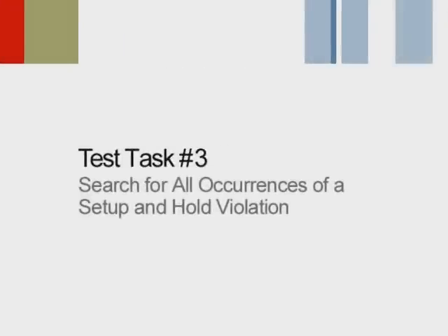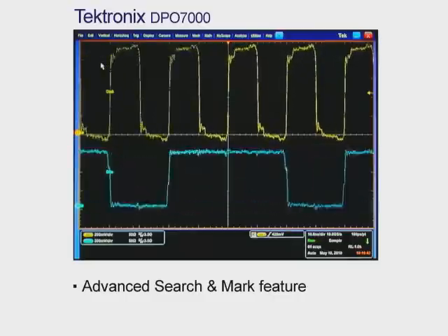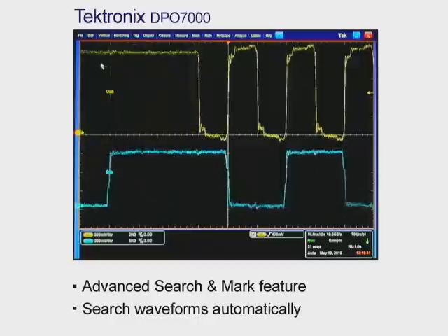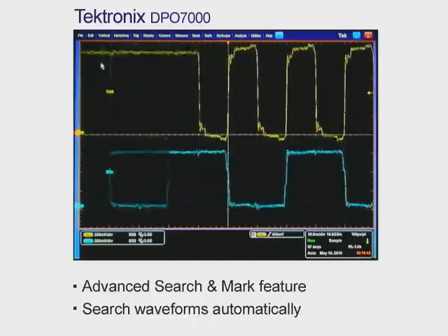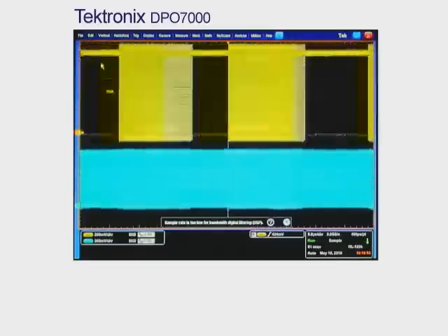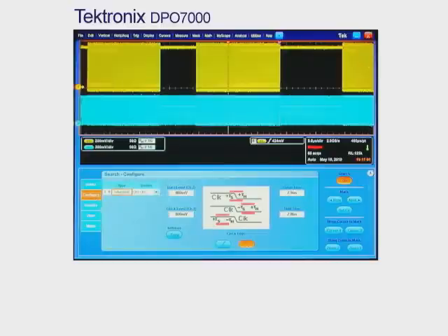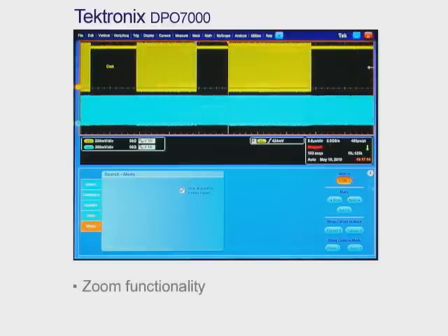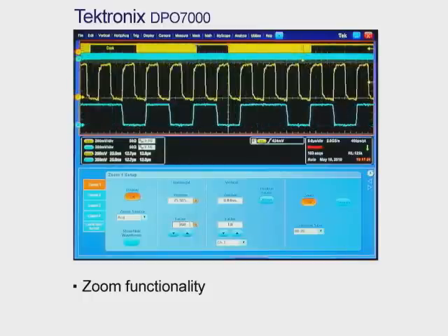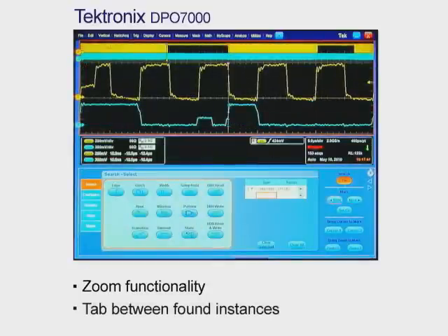Next, we want to search for obscure instances of a setup and hold violation on a captured clock and data signal. Here we see how quickly the Tektronix DPO7000 does just that. With the DPO7000's advanced search and mark feature, you can easily set up and automatically search the waveform looking for a specific setup and hold violation of two nanoseconds. First, we'll turn on the DPX display to see what's going on with the signal, then set up a search to look specifically for a setup and hold violation on the clock and data signal pair. The scope can directly go find that obscure instance in the record. Once we have it, we can use the zoom functionality to look for the setup and hold violation to see exactly what's causing it. Now let's search again for the next instance — see how easy it is to tab ahead and find it?